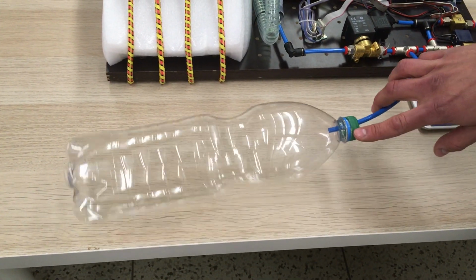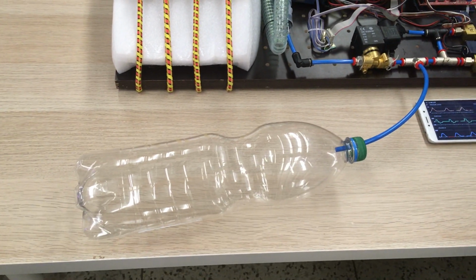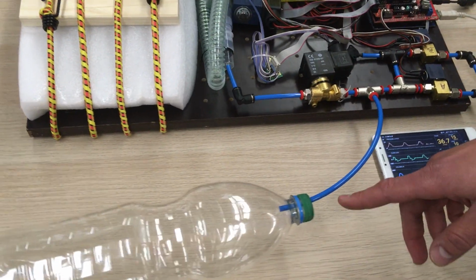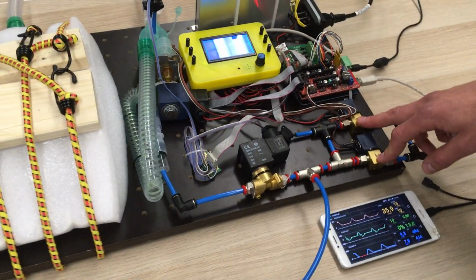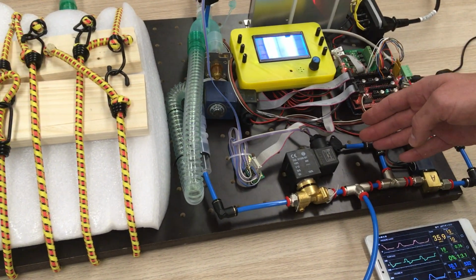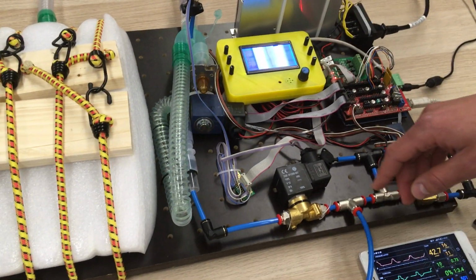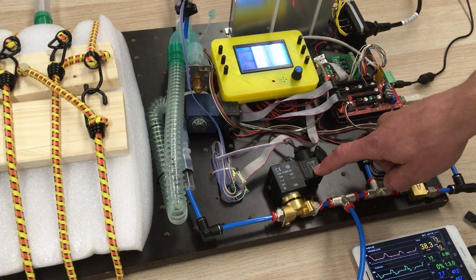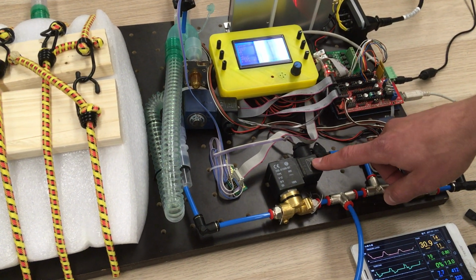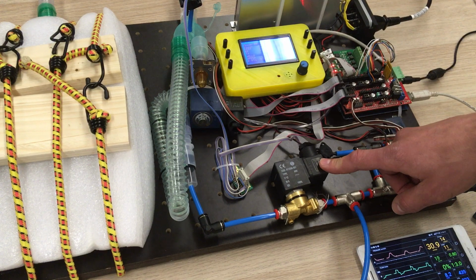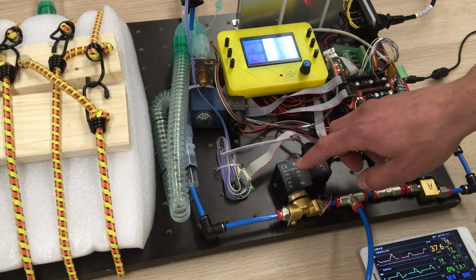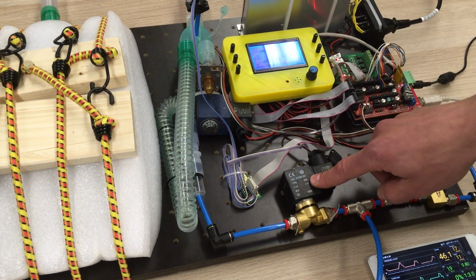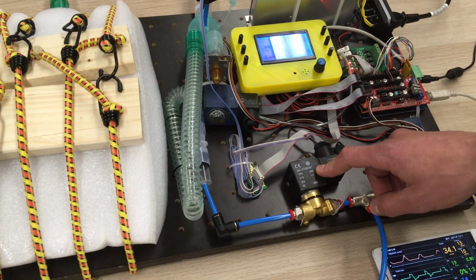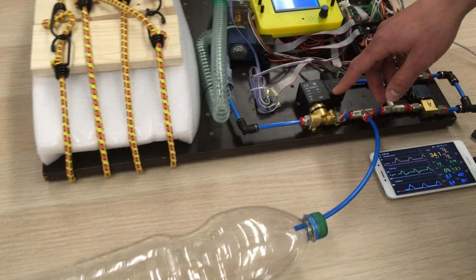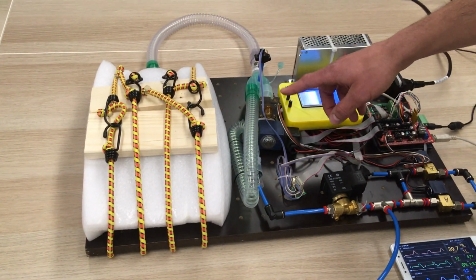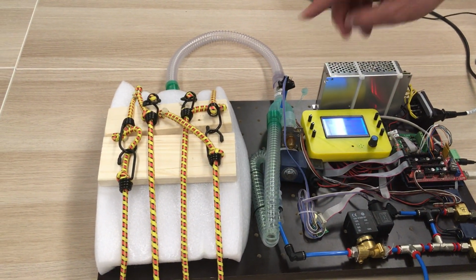So this bottle is used as a reservoir into which we prepare the proper mixture of air and oxygen at the desired pressure, and then another solenoid valve is used to control inhalation. So the inhalation, or inspiration, starts by opening this valve when the air goes from the flask through these tubings up to the patient's lungs.